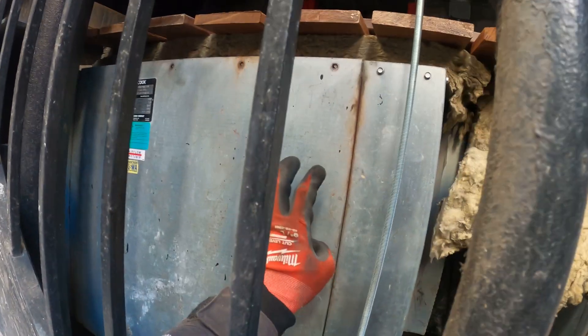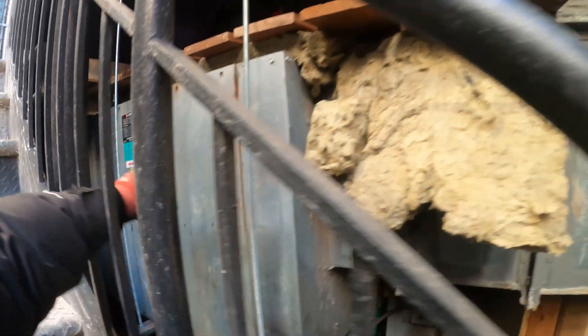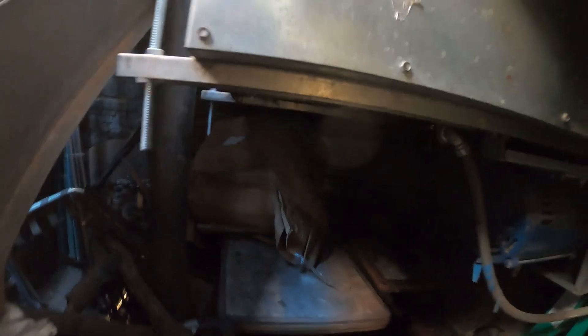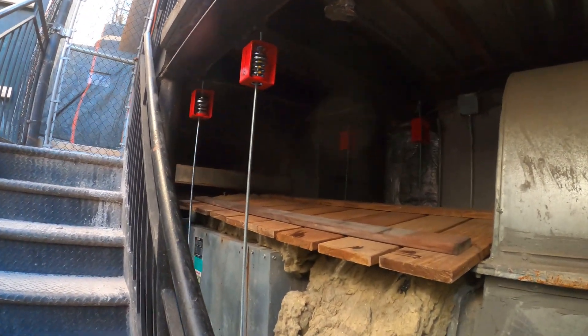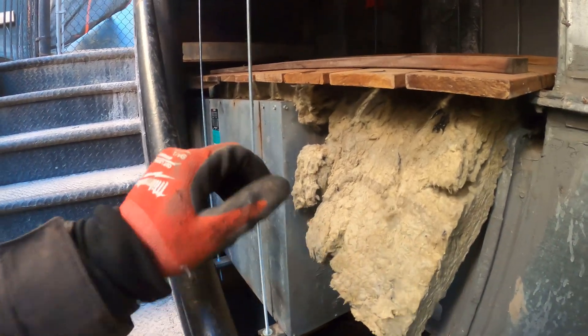That looks great. Got the fan on, gotta get some screws here — there's no screws. Just got a little bit of shaking; it's the covers. But everything sounds a lot better, and this thing is not one threaded rod away from being on the floor. Everything's nice and leveled, threaded rods cut, new nuts and bolts. See that cover shaking — get some screws on there. What would be good is if they had vibration pads underneath this. I tightened down the screw for the motor, changed the belt, four new vibration isolators, new threaded rod, new nuts and bolts, greased the bearings. Let's give this thing a shot.